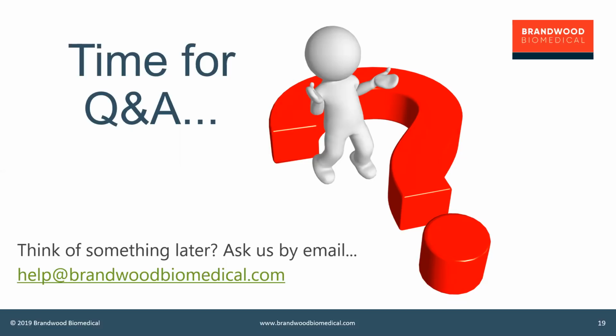Now, the content of that GSPR is located in Annex 1 of the MDR, so that's easy enough. But again, I don't believe the content is terribly unique. Now, there are some unique things in it, and you need to be able to address those individually, but the majority of what you're putting together for an ER checklist will be something that you can put into the GSPR checklist.